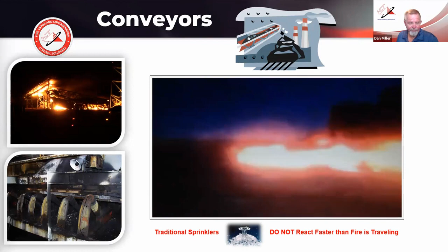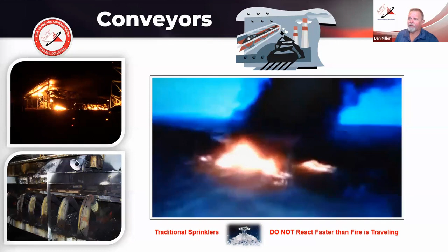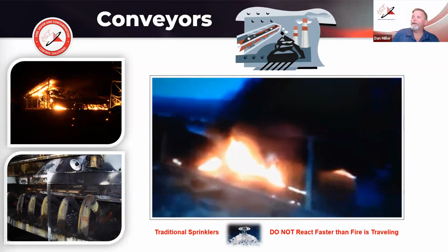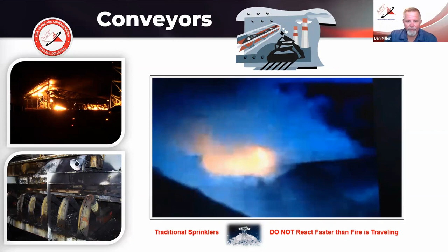An explosion and/or deflagration causes very fast fire travel, and sprinklers don't react fast enough to occur, prevent, or mitigate that. So we really need a system that can detect those problems early and quickly, and a deluge system, because a closed head won't detect or open fast enough to control the problem. So you need a deluge system with advanced detection involving things like infrared black body detection and so forth - things that are fast acting and reacting to manage that, along with the prevention program.